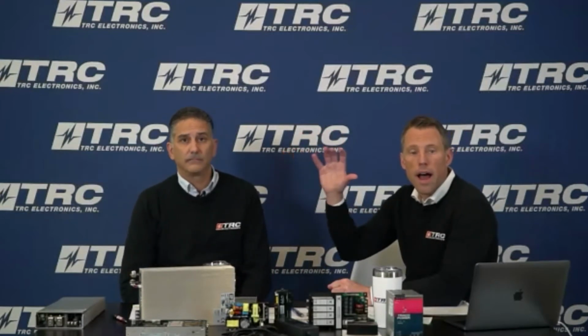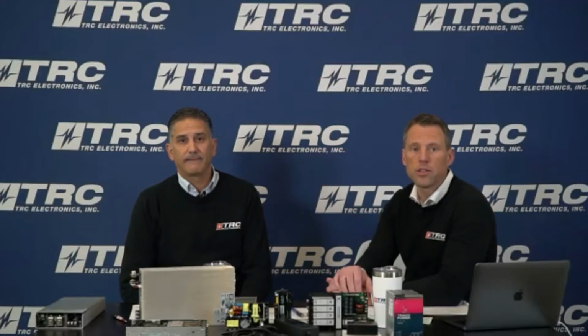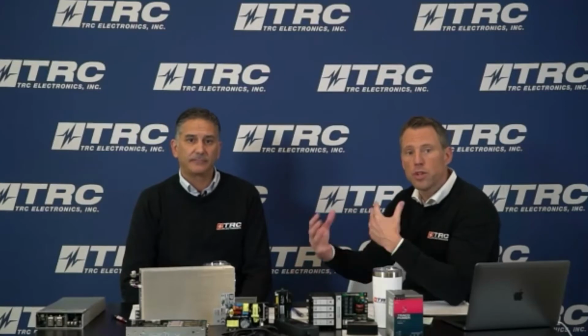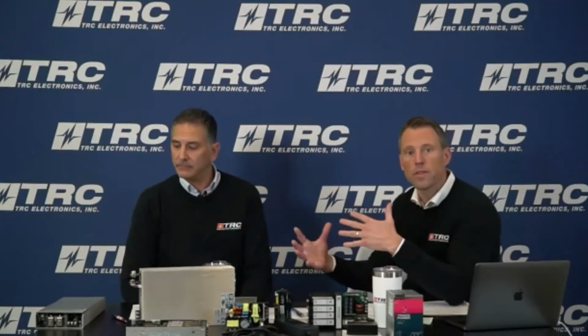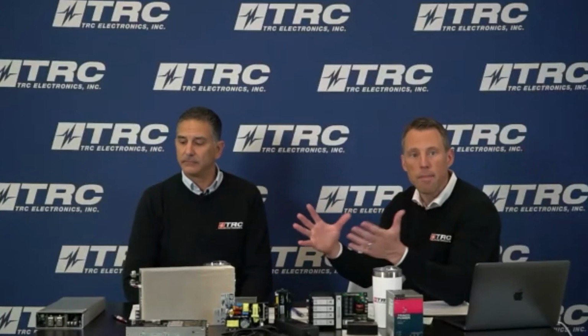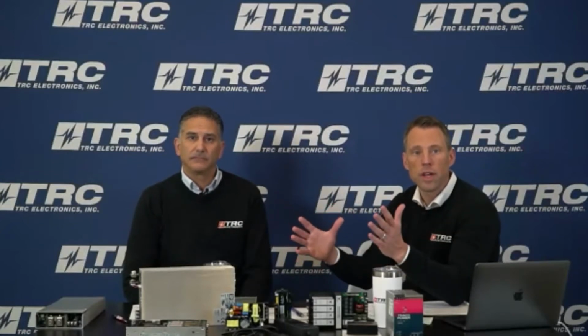All power supplies will have an AC derating curve, and knowing the exact AC voltages you'll be operating at is critical, because below 110 or 100 volts you could have derating. Even with a higher power application using a higher power supply, you could have maximum power at high line, but at low line, tremendous derating. Being aware of this and going through that process can save you a lot of time, because once you go through selection, get your prototypes, and test in a particular environment, you may overlook something, and now everyone's asking why you didn't think about that.